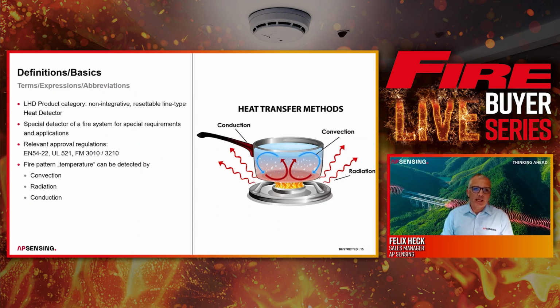The fire pattern, the temperature we are measuring, can be convected. For example, convected heat is rising heat because of the heat itself. A burning car in a tunnel or in a parking garage, the heat will rise to the ceiling, and this is convected heat. We can measure also radiated heat. For example, as I mentioned, the conveyor belt. Yeah, we cannot touch the conveyor, or the movement of the conveyor will blow away the heat from the roller itself. So we measure radiated heat on a conveyor or on a machine.